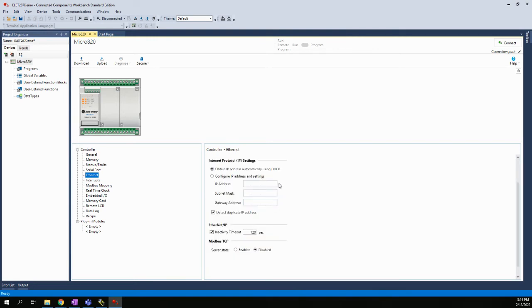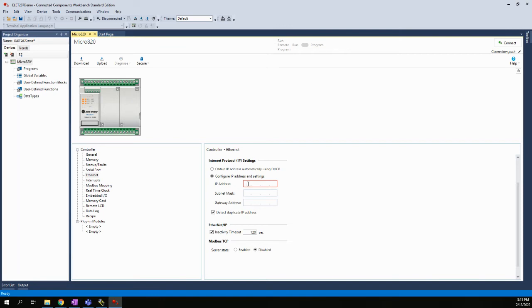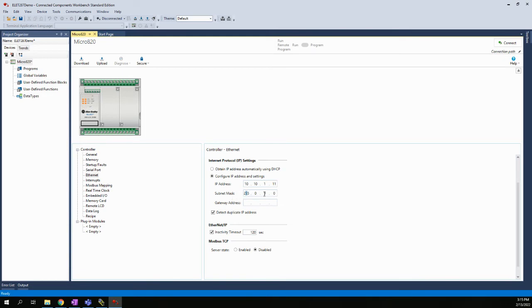Well, we don't want that, like we talked about in that previous video. We want to set what we call a static IP address, something that's fixed. It's also very important at this point that you type in the IP address that is actually in the controller. Because if you typed in a different number here, it's going to overwrite and change that setting in the controller. So ideally, we don't want to do that. So the IP address that is currently set to your controller is 10.10.1.11. Now again, the subnet mask populates automatically with 255.0.0.0, and that is perfectly fine to keep it like that. Or if you wanted to, you could go ahead and do the 255.255 in octets 2 and 3. But again, making sure to leave the last octet as a 0. Don't change that. And then the gateway can stay default. That's it. There is no accept or okay.